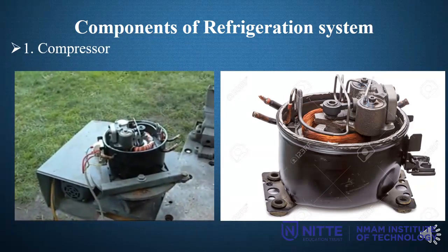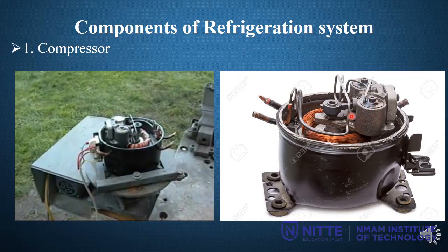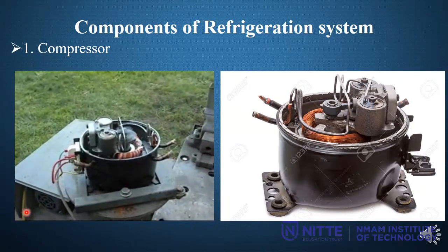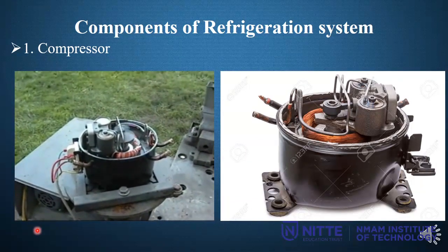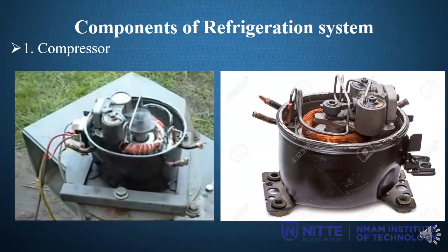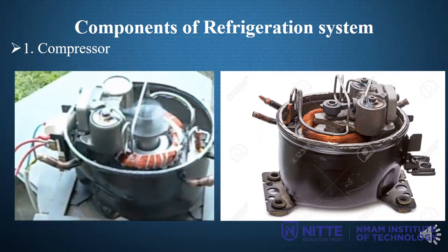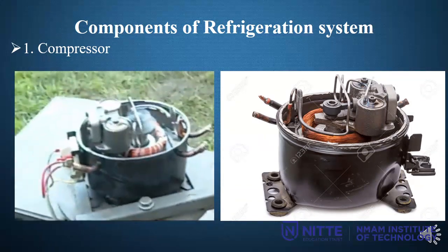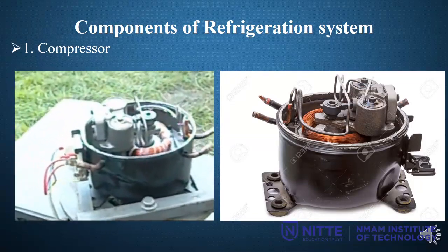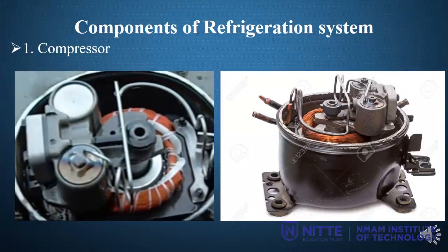This is a test run of a low start torque domestic refrigeration compressor to demonstrate the lubrication system. The whole setup is inserted in a coolant. You can also see how the refrigerant moves. It's going everywhere. Very effective. Okay, I'm going to switch this off. So this is how the compressor works.